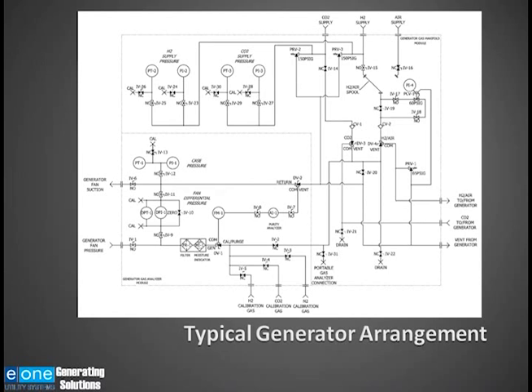Very important, and I lost my pointer, so I can't point this out, but up in the upper right-hand corner, there's a H2 air spool piece. And this is a removable piece that will not allow you to put hydrogen and air in the generator at the same time. This is not foolproof. This does not eliminate the chance, but it minimizes the chance. And I'll point this out in the next slide.